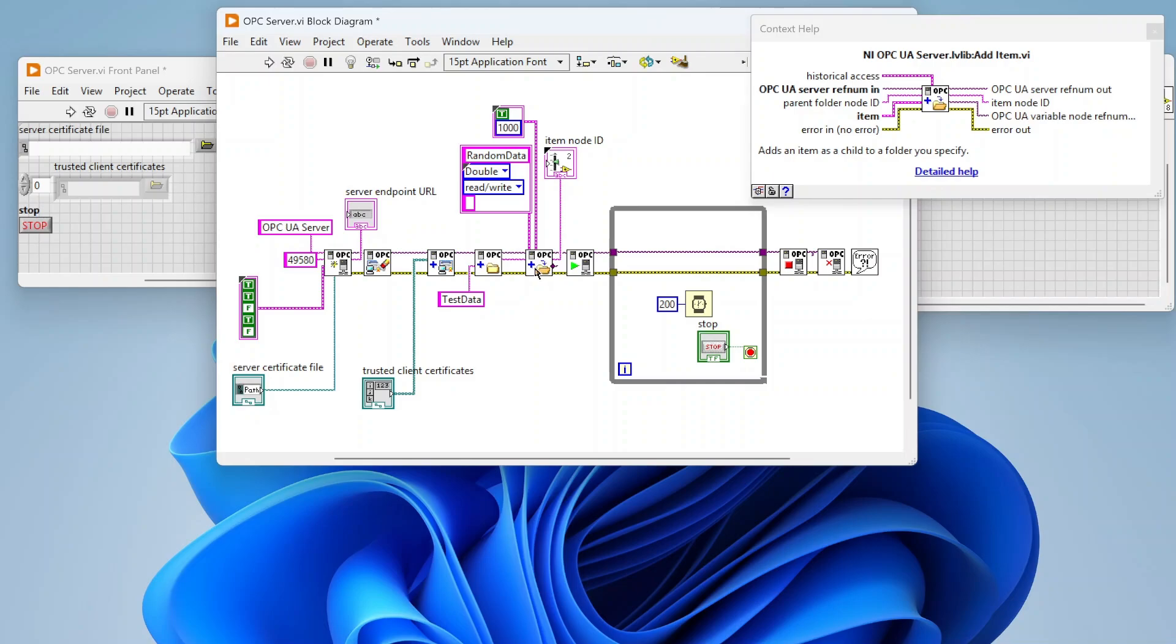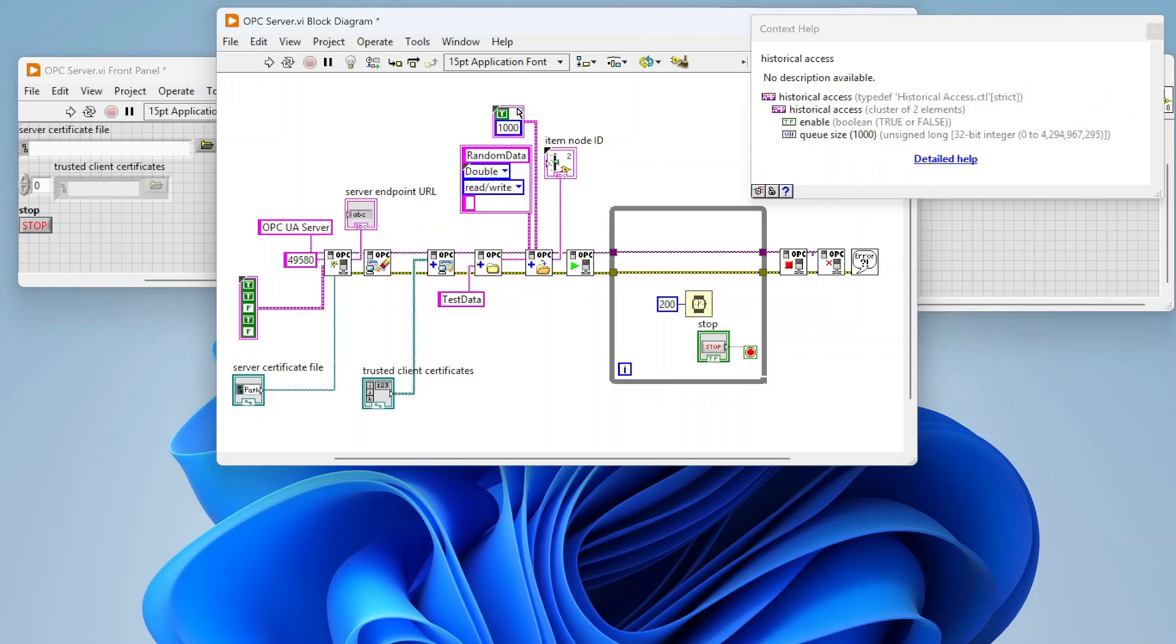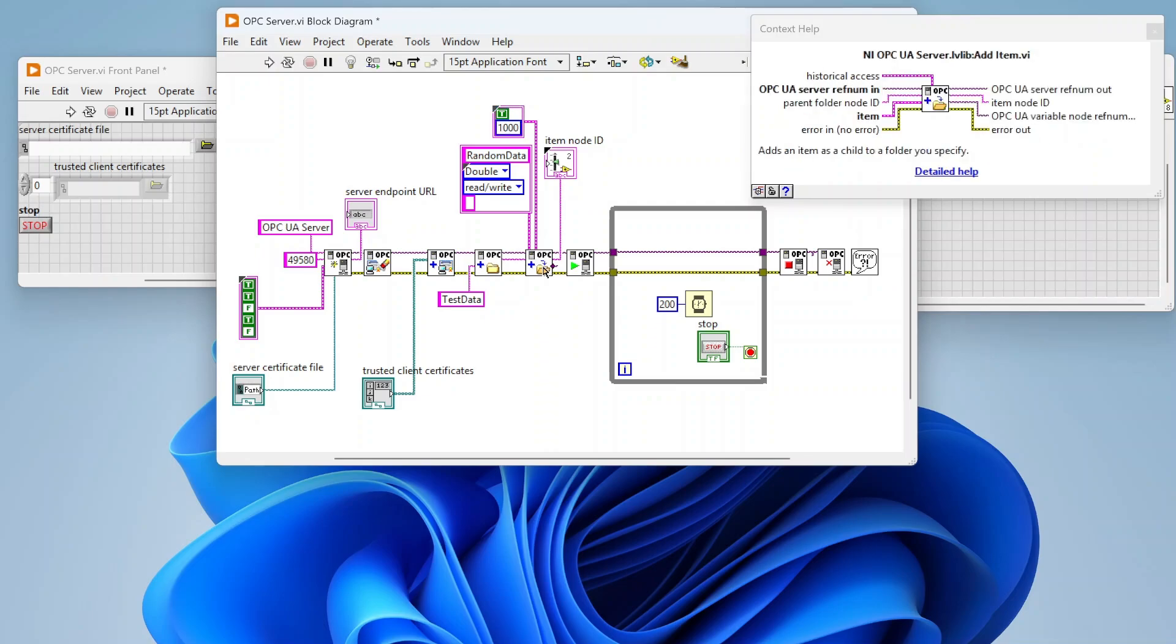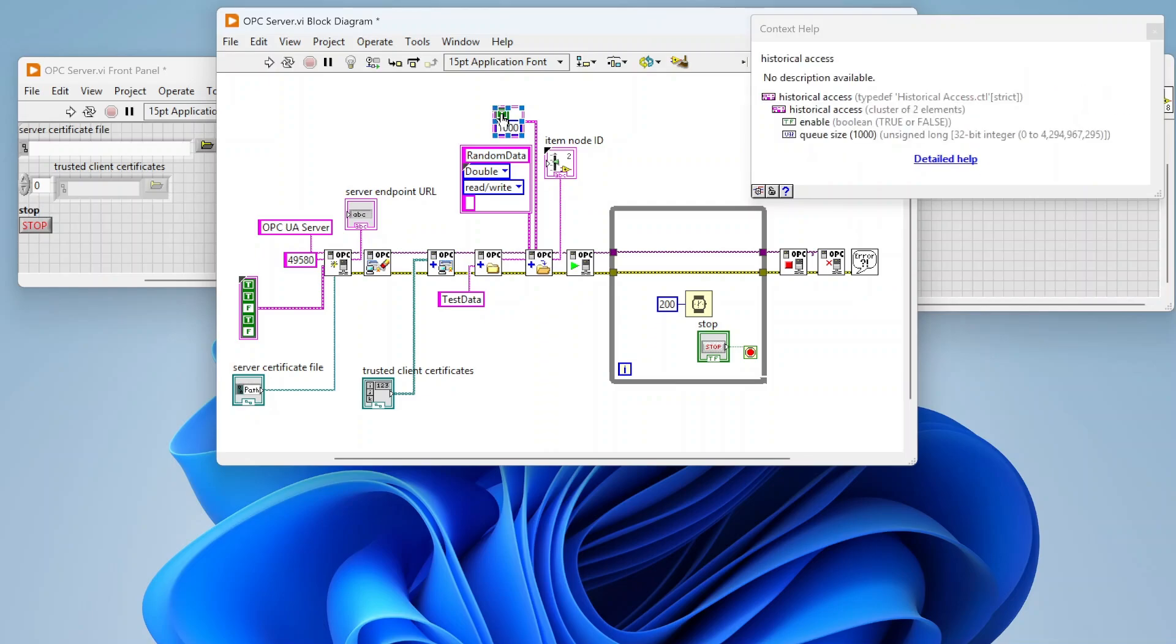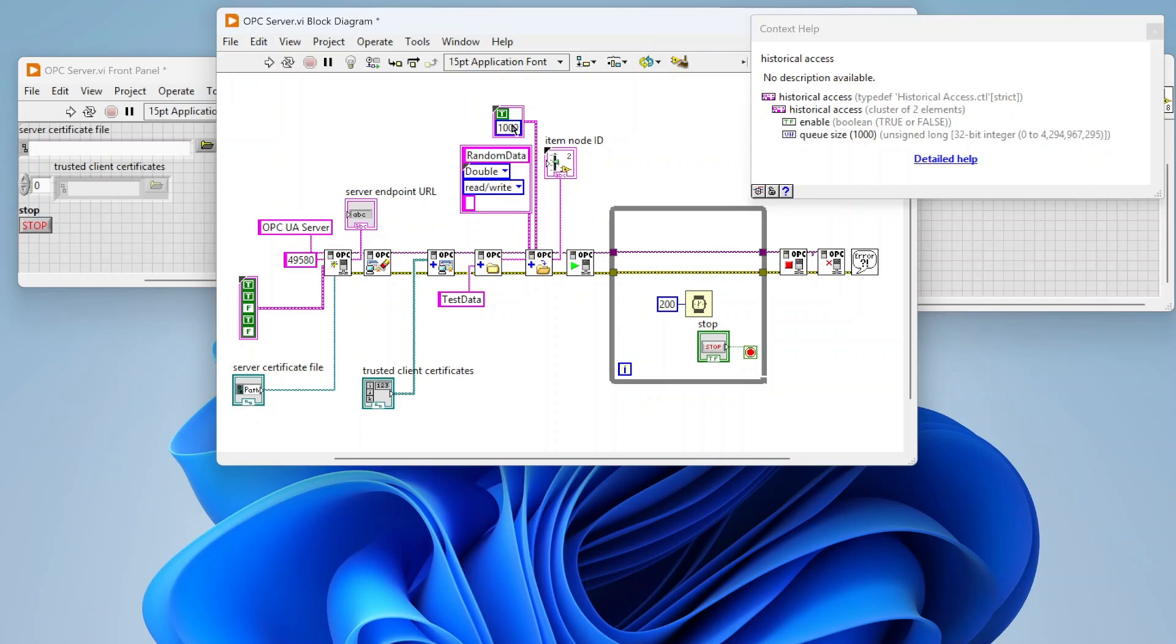Another really cool thing about OPC UA is it allows for storing historical data. There's this historical access option you can enable or disable. If you disable this, someone reading that data only gets the current value. But if I allow historical access, I can store a buffer of that data. In this instance the queue size I've set is 1000, so this will hold the last 1000 values for this item in memory. I can either read the current value or read the last 1000—it keeps like a circular buffer of that data. I can specify what I want that size to be.